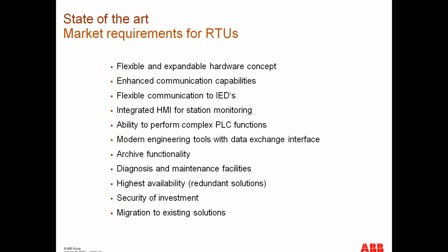Another market requirement was the archive functionality to see all what happened in the grid and what actions have been done in the past, to archive this. Then another requirement is diagnosis and maintenance facilities, as well as, of course, highest possible availability, in brackets, redundant solutions, which means that if one communication unit in one RTU fails, there's the possibility another communication unit, let's say as a hot standby, takes over.